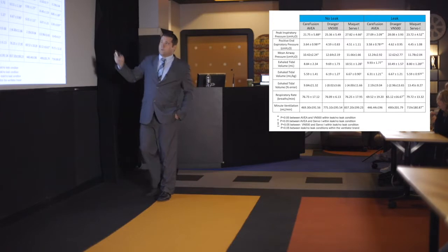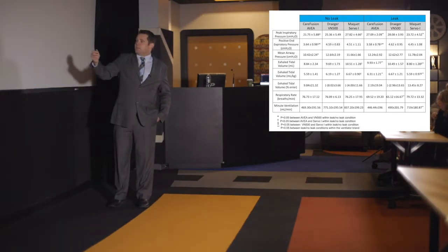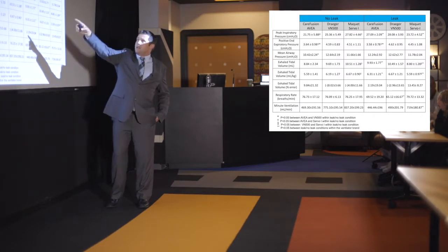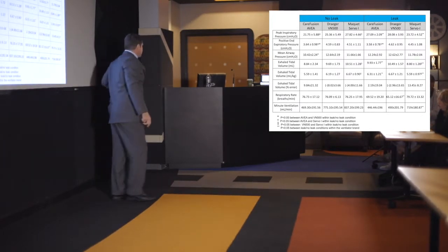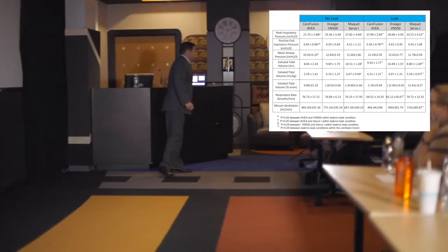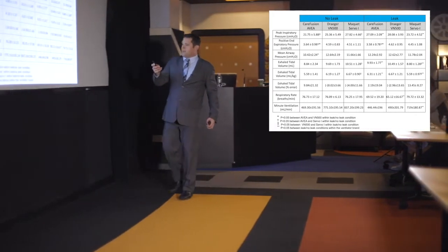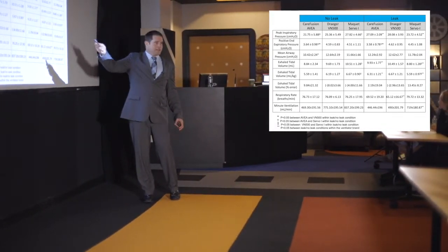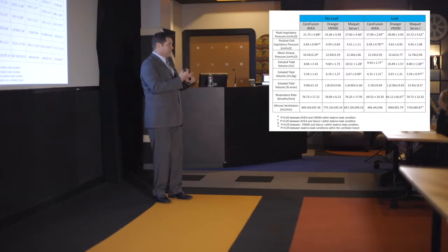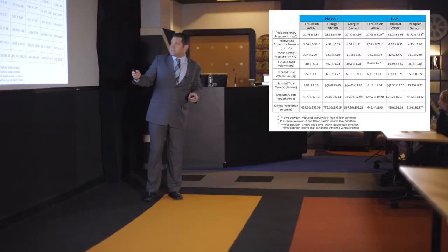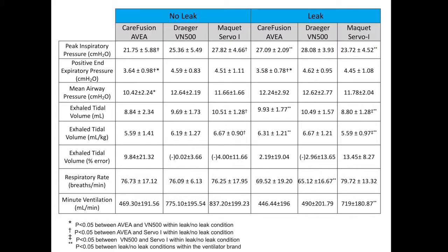And then we loosen it up so that we implement an ET tube leak at 20 centimeters of water pressure. And it's pretty interesting what happens, because each of the animals is supported with all of these different ventilators with identical settings. And what I think is pretty interesting is that this thing doesn't work. And if you look at the peak inspiratory pressures on the upper line over there, you can observe that the pressures are generally within the range that we need to have, but the Maquet was a little bit higher, right? Because you're adjusting pressure based on your tubing compliance factor back at the ventilator valve. So that has a tendency sometimes to overshoot or undershoot the tidal volume. But in this case, without the endotracheal tube leak, it wasn't horrible. It was only off by about 4%. And the respiratory rates were all similar.